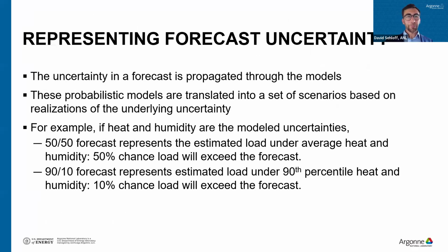Finally, there are clear ways of handling uncertainty in load forecasts. The forecast will include a representation of uncertainty and propagate it through the modeling, and we then need to translate these probabilistic models into a set of concrete scenarios to realize the underlying uncertainty. As a quick example, if we have heat and humidity as the uncertainties, we have what's called a 50-50 forecast, which is the load estimated under average heat and humidity, so there's a 50% chance the load will exceed this forecast. A 90-10 forecast is a more extreme forecast with the 90th percentile heat and humidity, capturing 90% of what we'd expect the load to possibly be.